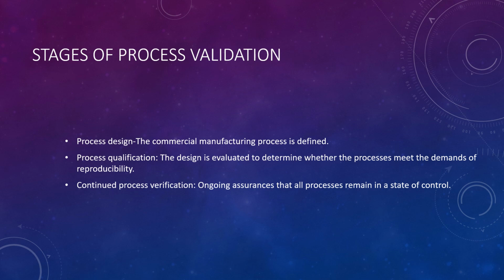Process qualification. The design is evaluated to determine whether the process meets the demands of reproducibility. This is the stage where the process that has been defined gives results which can be reproduced at any time by anyone and in whatever circumstance, maintaining all specification limits and all operational parameter limits. So all this will be evaluated during process qualification.